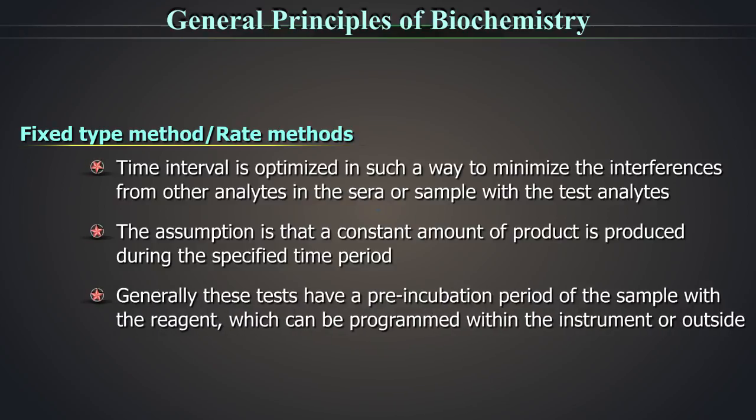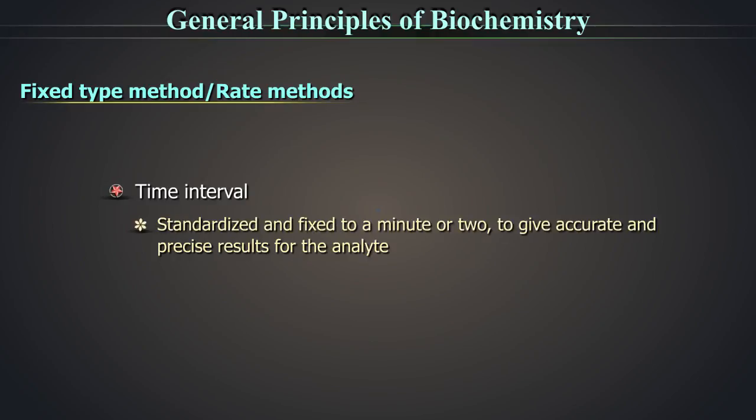Generally, these tests have a pre-incubation period of the sample with the reagent, which can be programmed within the instrument or outside. It is during this period that any substance other than the test analyte present in the sample, which could react and interfere with the reagent system is removed completely. The time interval is standardized and usually fixed to a minute or two to give accurate and precise results for the analyte being estimated.